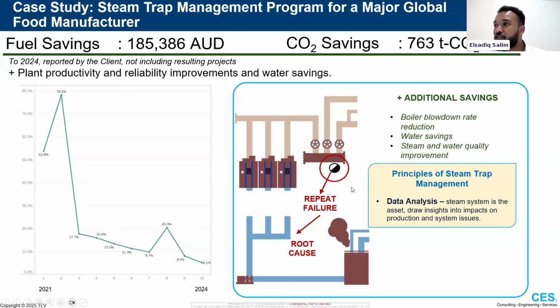And then one case study on the right of why that repeat testing is so important: they had a repeat failure on the steam distribution header, and because it was a repeat failure—even with replacements it kept happening—by looking through the data, it triggered an investigation into their water system.